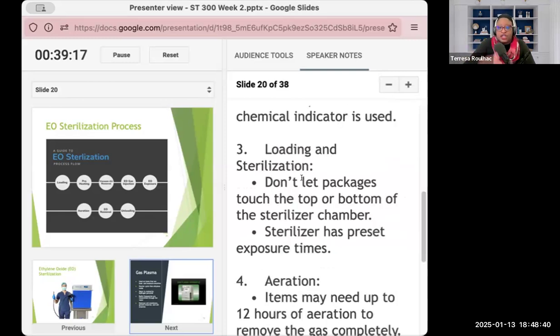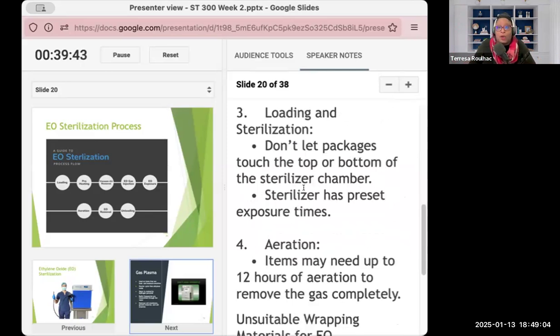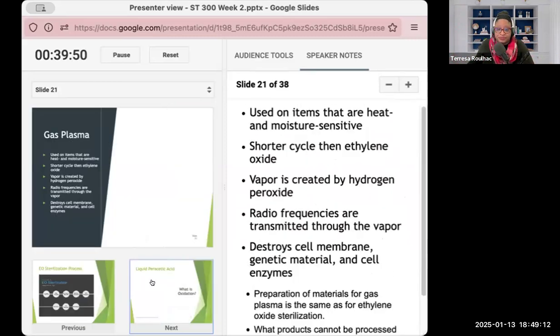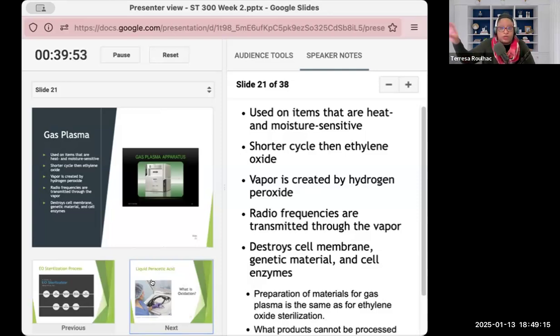Do not let packages touch the bottom or the top of the sterilizing chamber. So you're kind of pulling them in, giving space all around. Think about it. If you have it touching the walls, it's not going to have room for all of the steam or even the sterilizer material to touch every aspect of that item. And with aeration or the drying time, items may take up to 12 hours after you've removed it for the gas to completely be out of the item. And I try to get images so you can kind of see how the machines look differently.